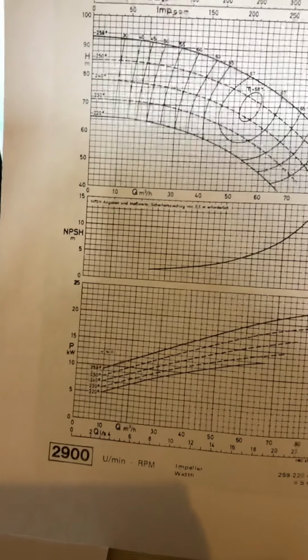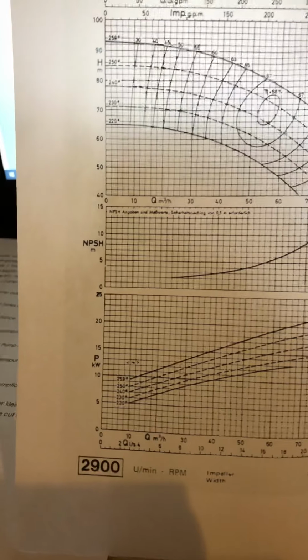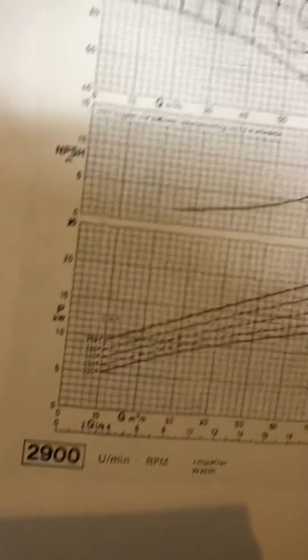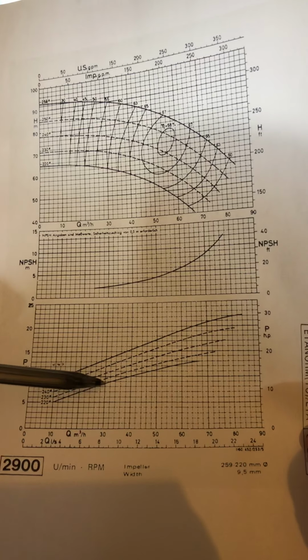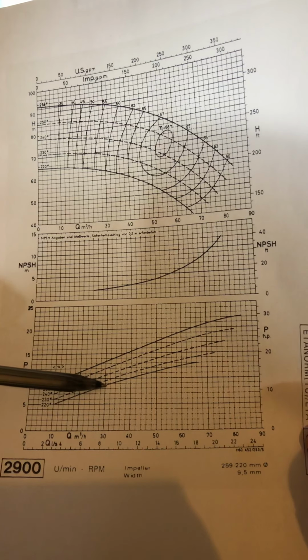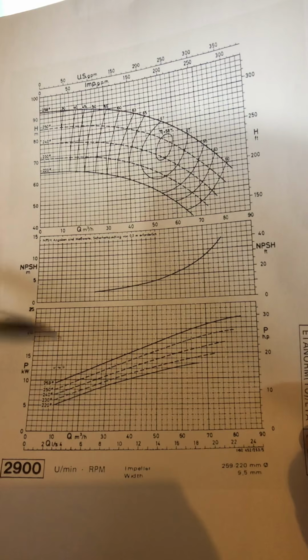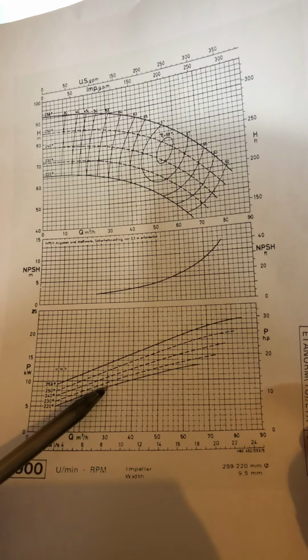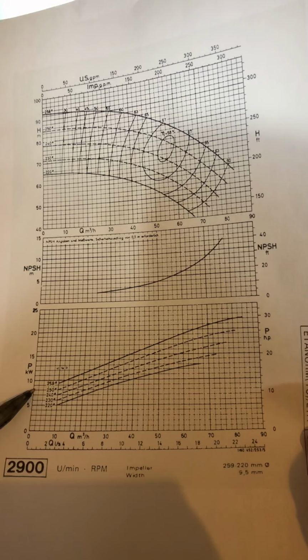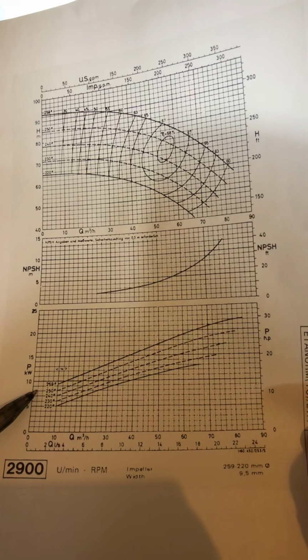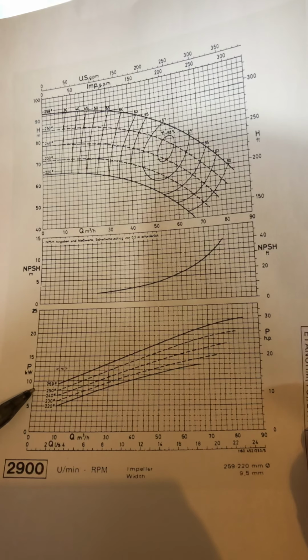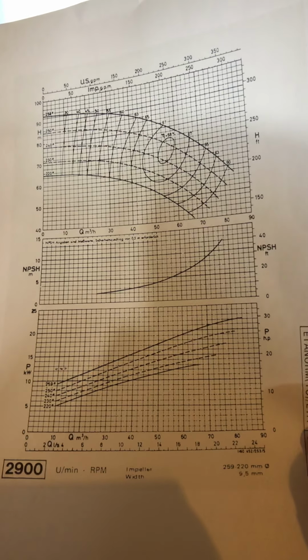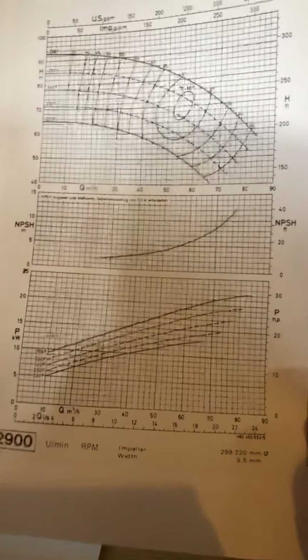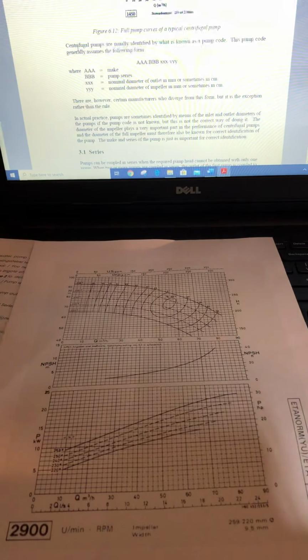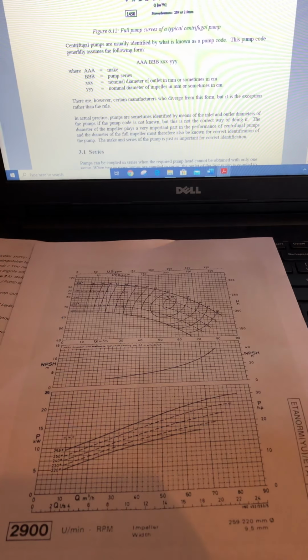And so the last important thing I could ask you is the power consumption at duty point. You are still at 30, you are still at 220, so that's that line. Now you want to calculate the power consumption, so it'll be that line, and you work that right back to there, and it seems like it cuts between 8 and 9, let's say 9 maybe. So maybe just say 9 kilowatts. And that is all you need to know for pumps and calculation of pumps.